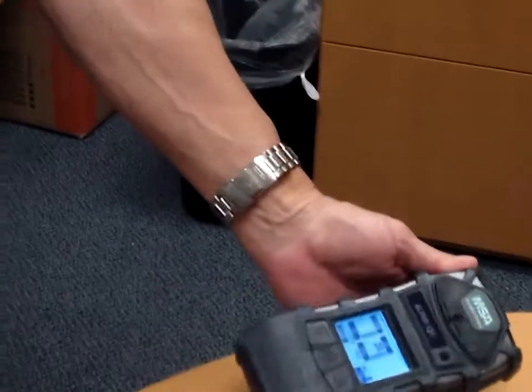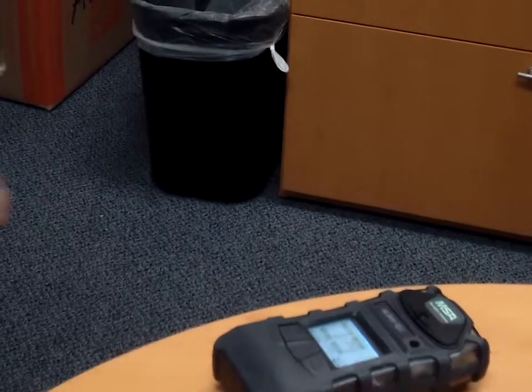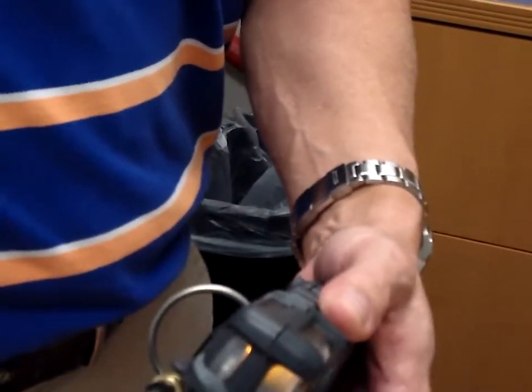Ah, there's our alarm. Okay, I'll disable that in just a moment. Okay, so this connects to the probe here as a quick connect, just like so. And then this end attaches onto the top of the unit. It will probably go into an alarm, and the reason it will is because it's drawing a quick vacuum. It all of a sudden had to draw the air through there.